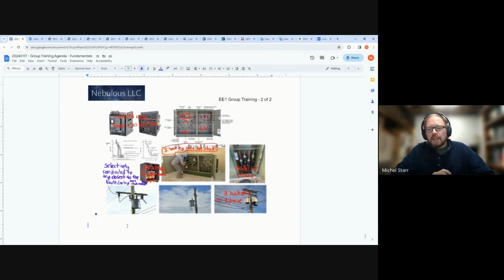It isn't that you'd see sparking directly using an infrared gun through a window to view the terminations, but you will see increased heat if there are loose bolts. This gives an indication of how soon a problem is to come, or that there's no problem. You should see even heating between the phases of a three-phase system.